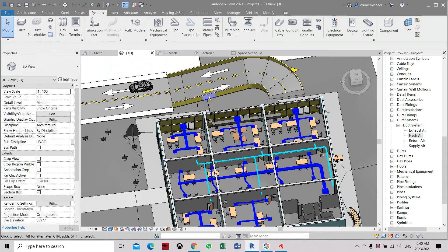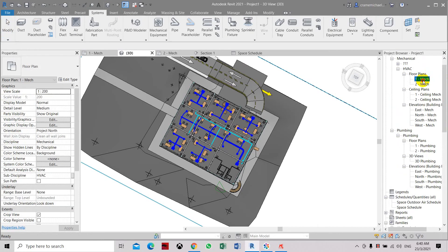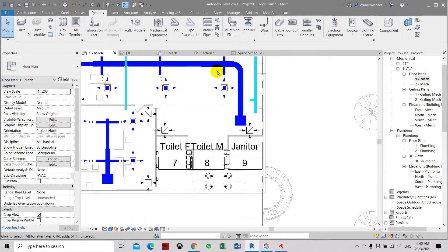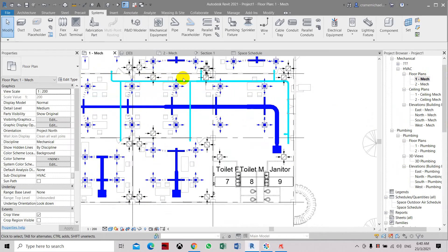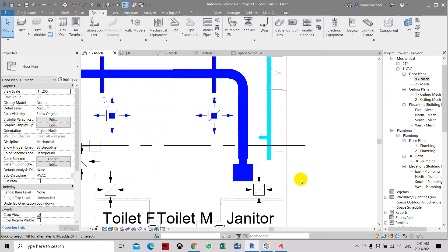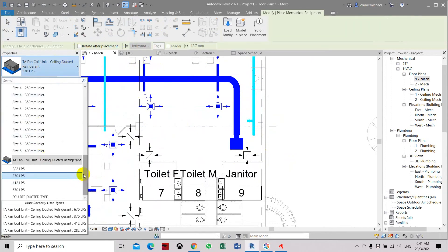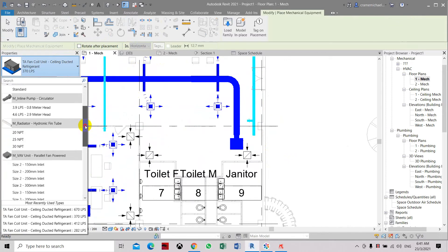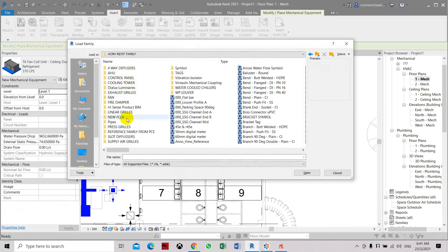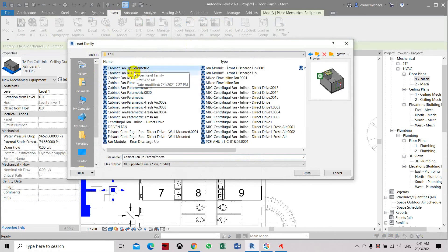Let's go to the 3D view - here we have the fresh air duct. Let's go back to level one. Now we need to take in the air from this side and install a fan here to pump the air going into the indoor unit, because the length of the duct run is quite long and it cannot be sucked by the fan coil unit alone. So we need to insert a fan here. Let's go to the components and insert a small fan.